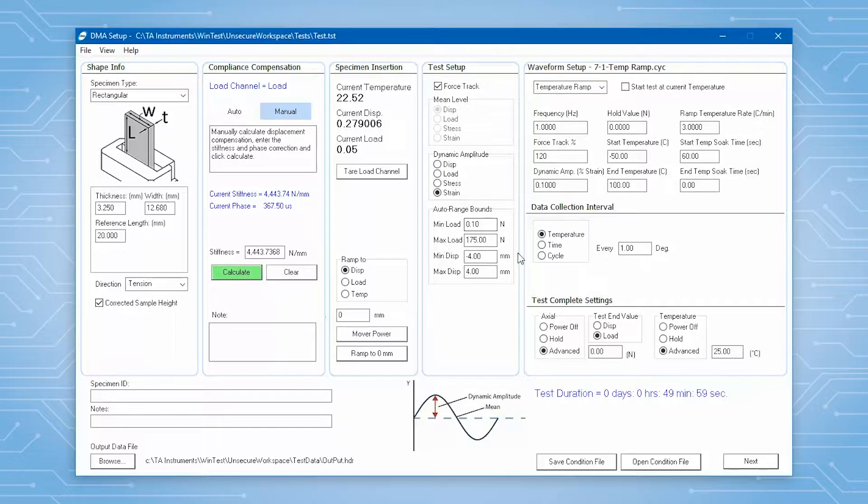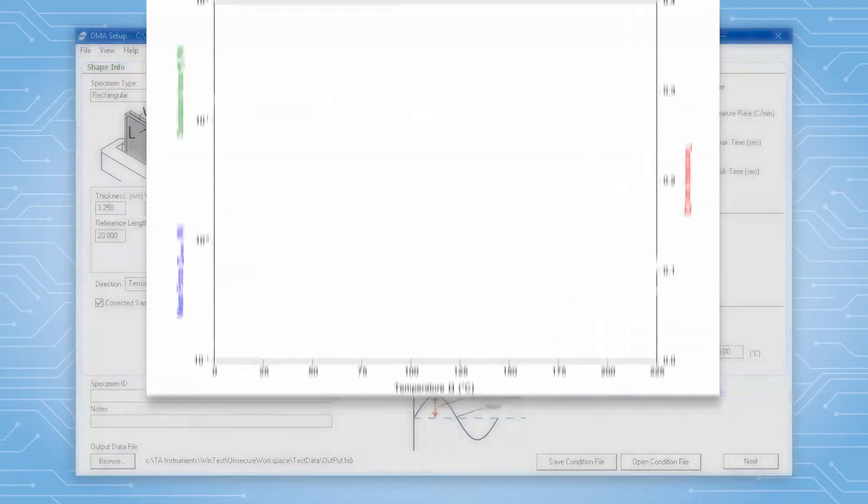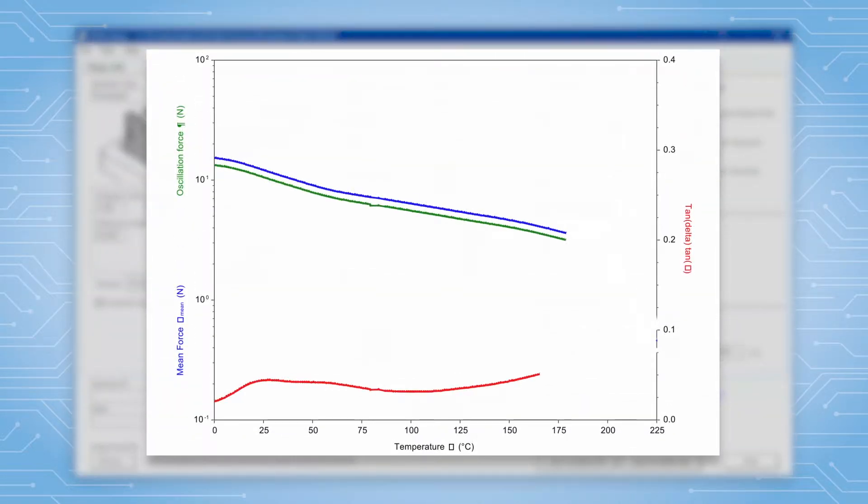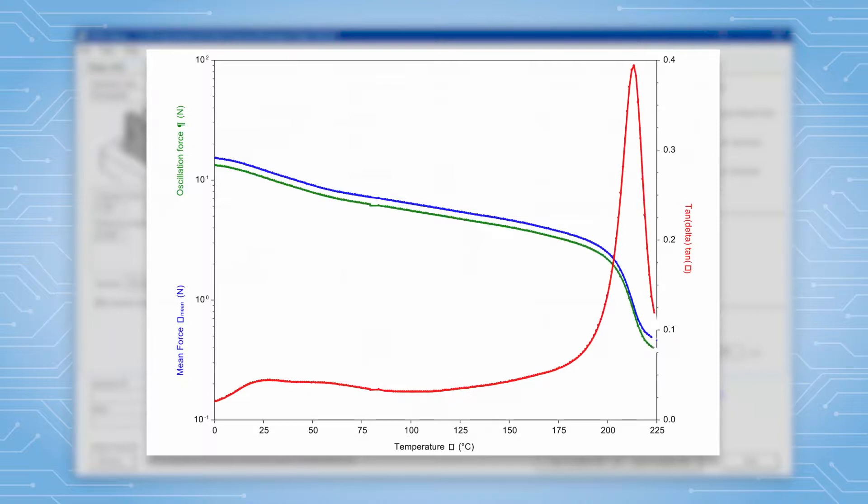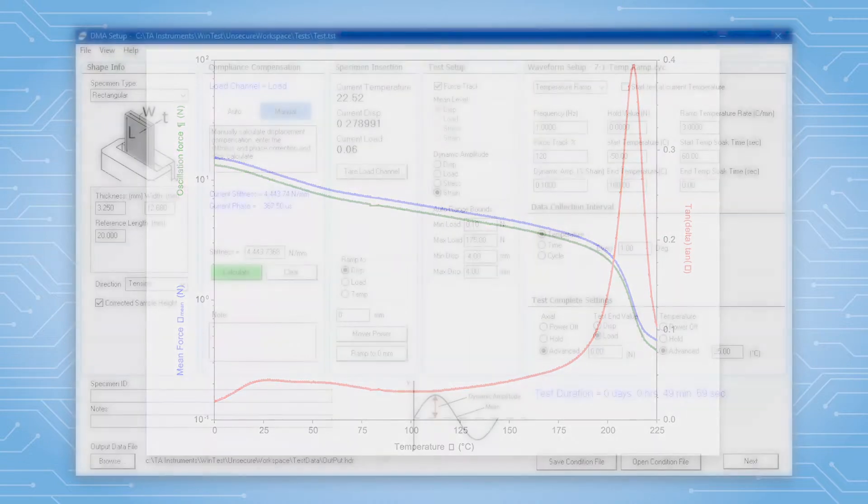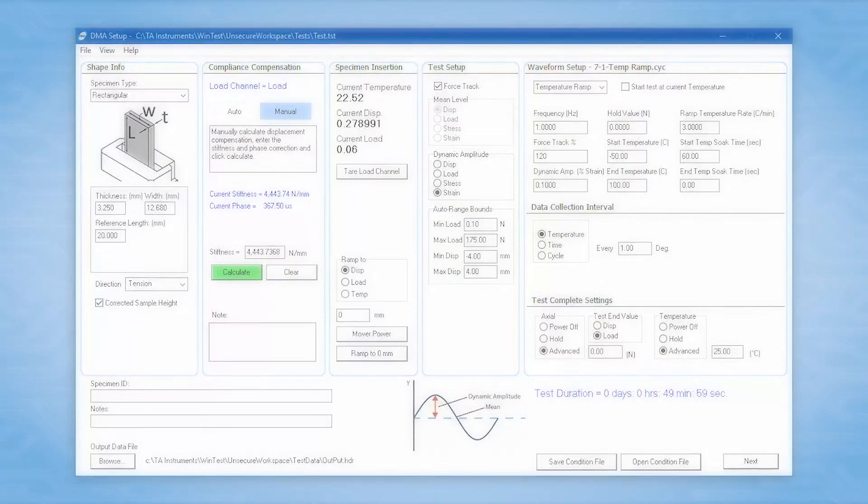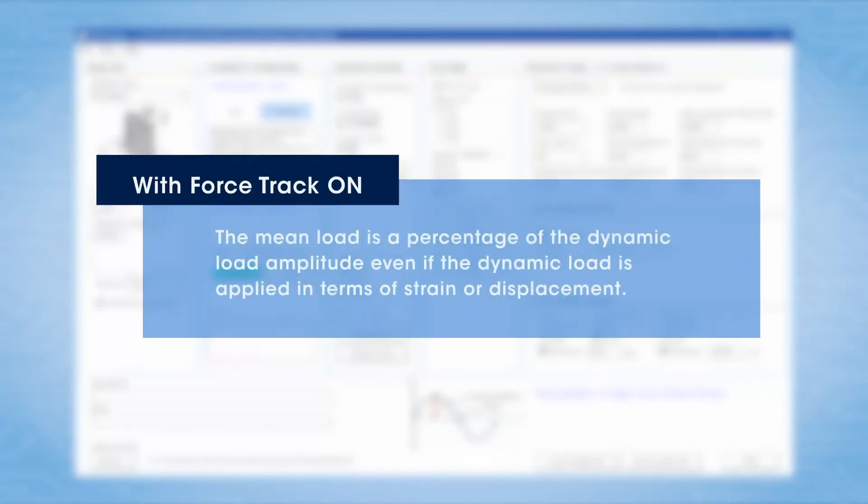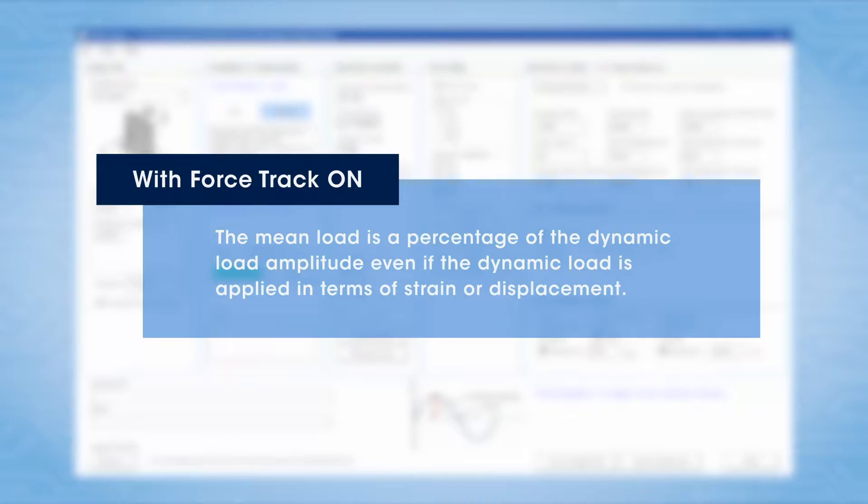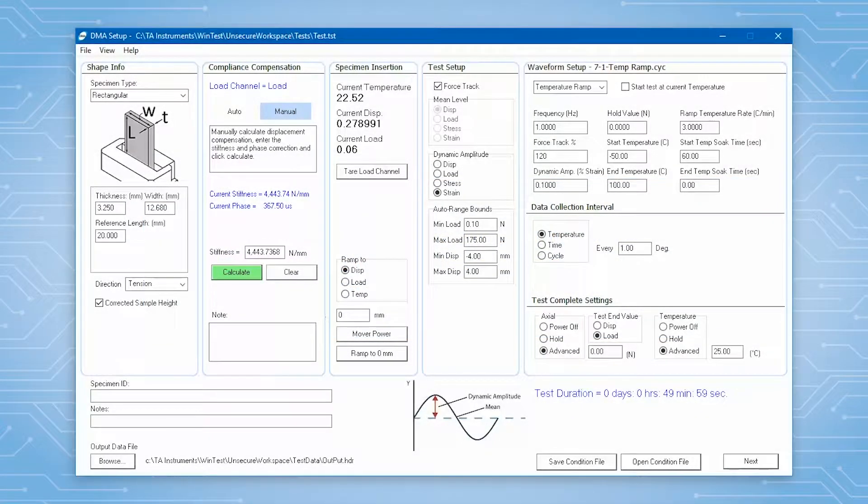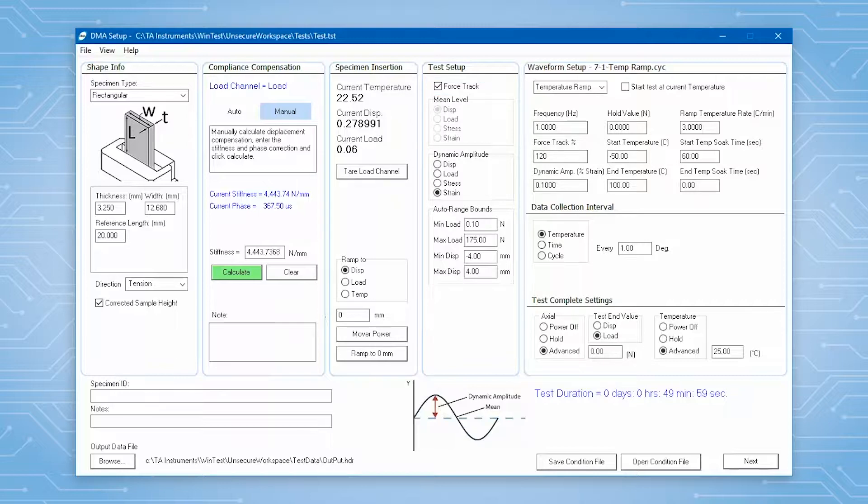It is difficult to predict sample creep beforehand. With force track, you do not need any advanced knowledge of the required mean load for a sample. You can just define the mean load as a percentage of the dynamic load amplitude even if the dynamic load is applied in terms of strain or displacement. If force track is selected, the mean level is automatically calculated by the system.